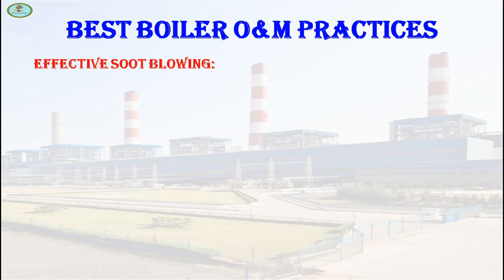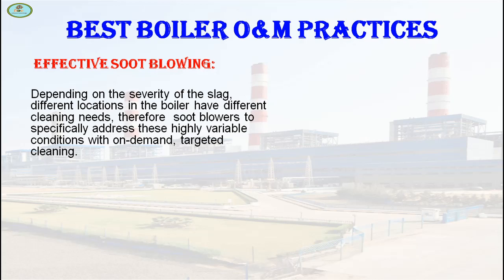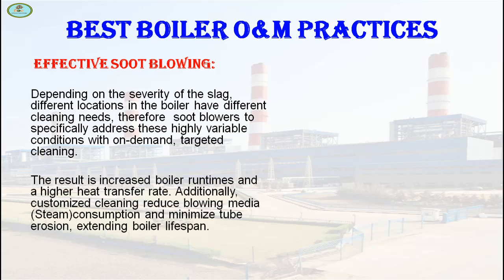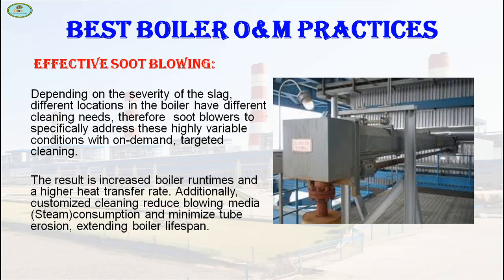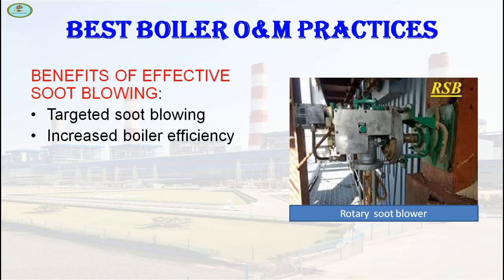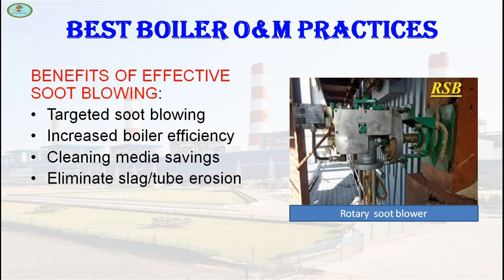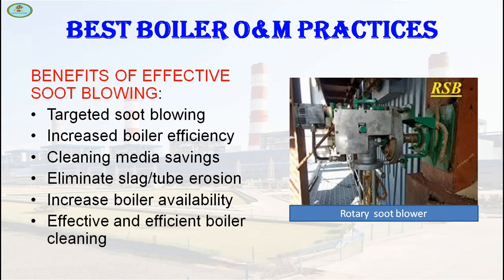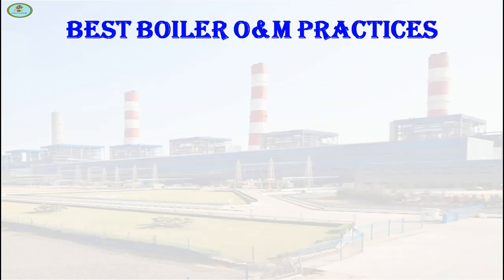The first one is effective soot blowing. Depending on the severity of the slag and type of fuel used, different locations in the boiler have different cleaning needs. Soot blowers especially address these highly variable conditions on demand with targeted cleaning. The result of soot blowing is increased boiler uptime and higher heat transfer rate. Customized cleaning reduces steam consumption and minimizes tube erosion, also extending boiler lifespan. Benefits include targeted soot blowing increasing boiler efficiency, reducing steam consumption, eliminating slag, improving boiler availability, and enabling effective and efficient boiler cleaning.